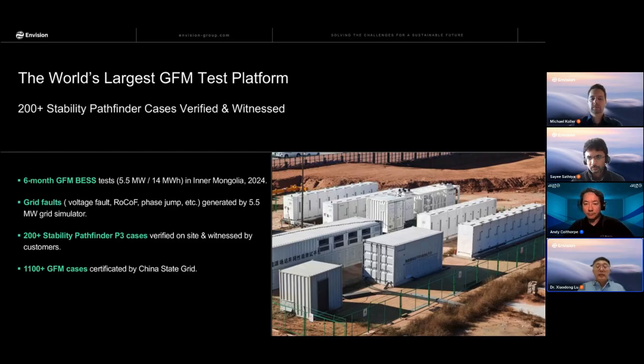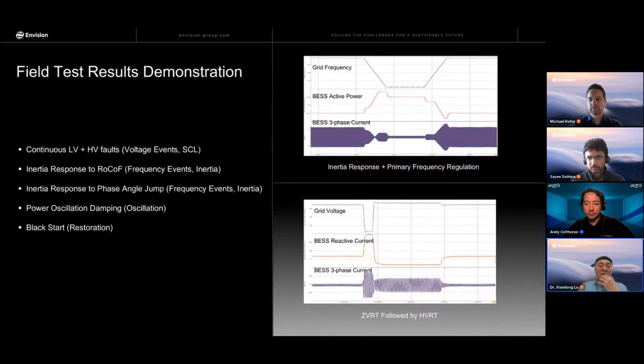Okay, that's the test, and here I have some field test results listed for demonstration. The first one is the voltage events or short circuit level, including both low voltage ride through and high voltage ride through. The second and third belong to the inertia: inertia response to the rate of change of frequency, and inertia response to the phase angle jump. And the fourth one is oscillation damping.